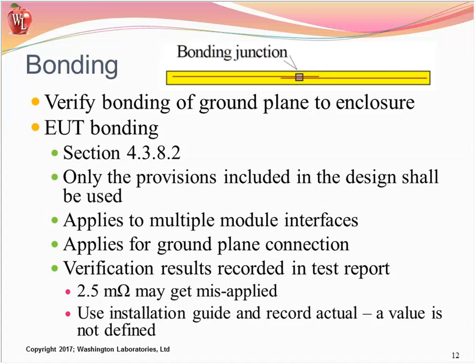The verification in the text calls for you to measure the grounding situation without additional grounds. So that indicates that you need to measure what you have installed with the ground connections that are used made, but not other grounds like shielded cables and the like that give us a parallel path for the bonding. We need to measure what it would be prior to all those actual things and record this in the report. The value is not defined, it needs to be what it is. So you should always consider using this as a means to say, I am matching the installation and my results of the grounding are indicative of what the actual installation is.